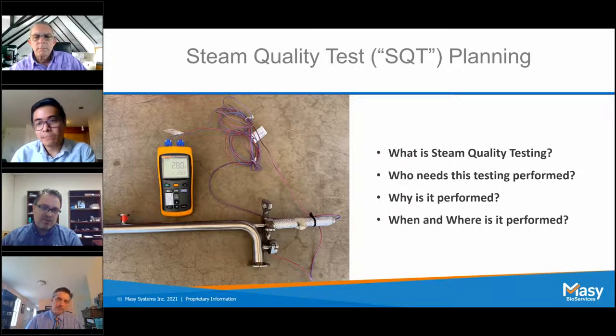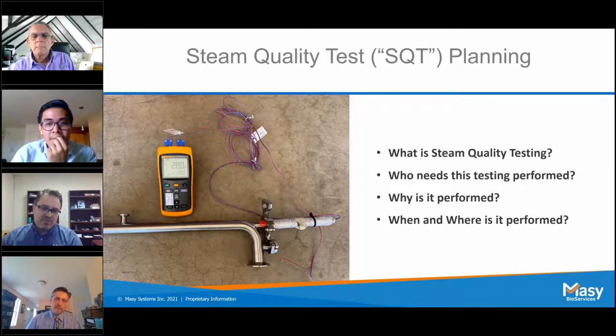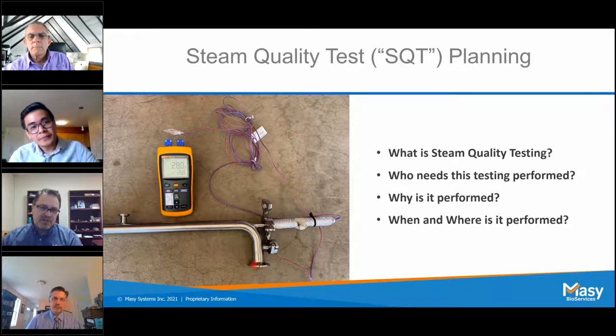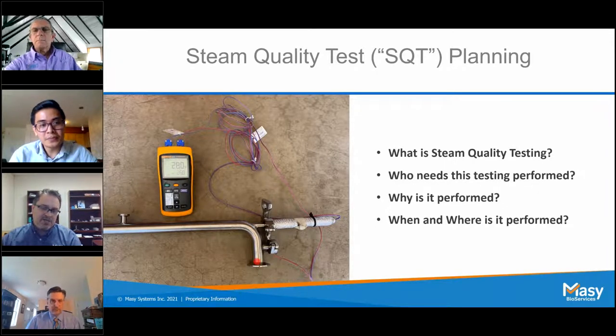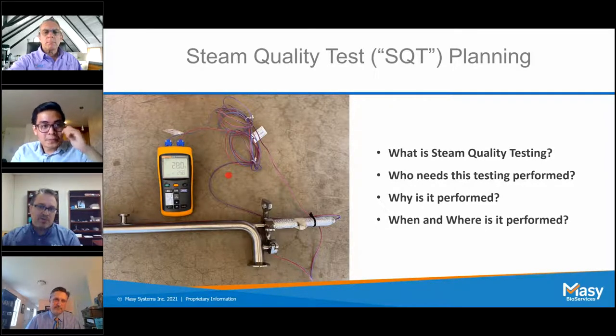Right there where that red dot is pointing, that's a supply line that goes into a condenser, which I'll speak to in a minute. Of the other two connections near the front, one goes to an expansion device that we use for testing for superheat, and another brings a thermocouple into the line so that we can measure the temperature of the steam. The bottom larger sanitary connection is for a steam trap, so that we have a way of removing condensate from the system while we're collecting our steam. In addition to those components, you'll see a Fluke temperature meter there with a couple of thermocouples, which are calibrated, and they are used to measure the temperature to support the testing that we're doing.